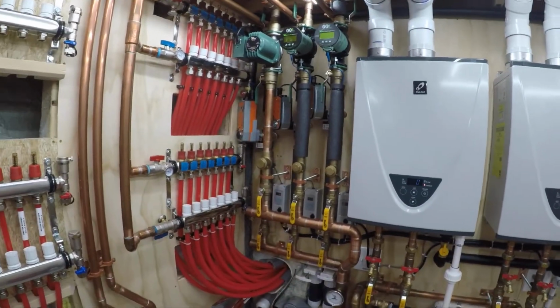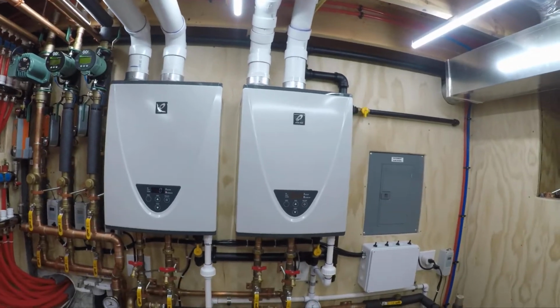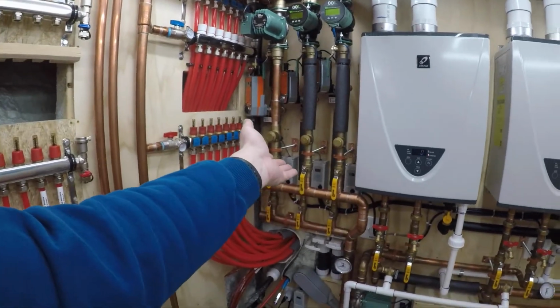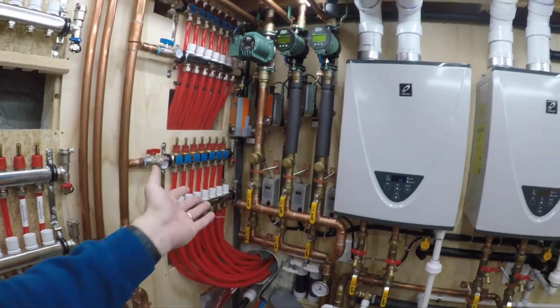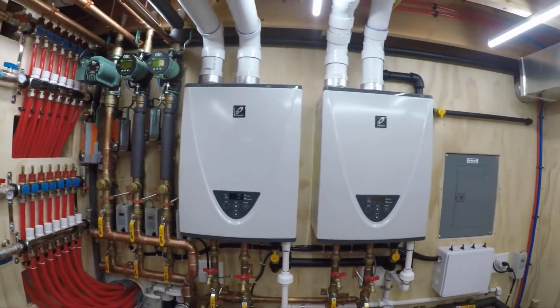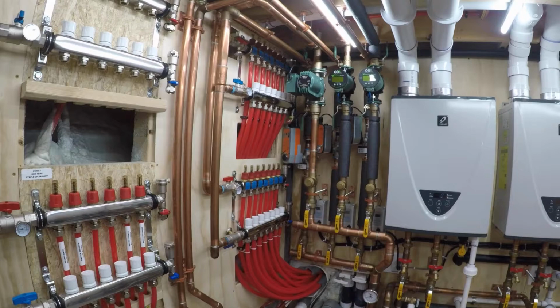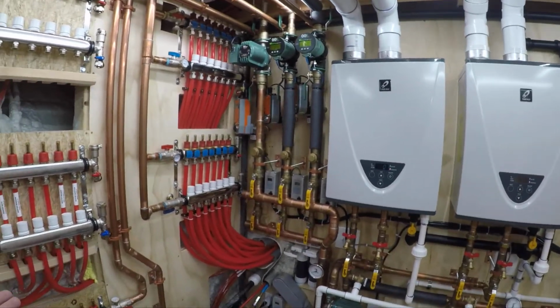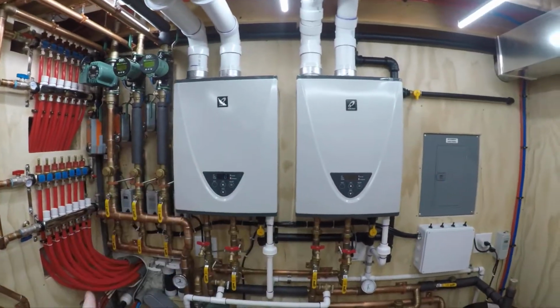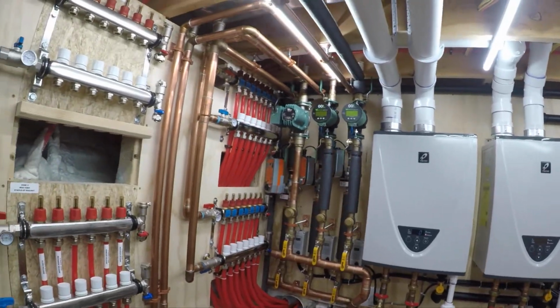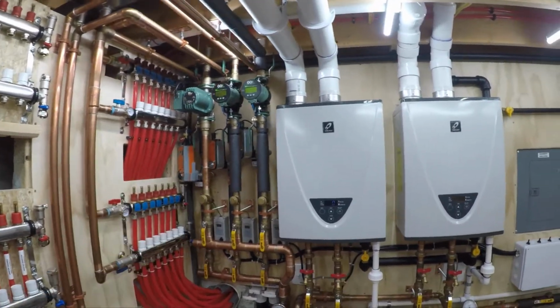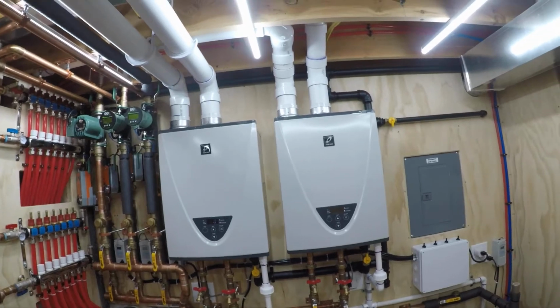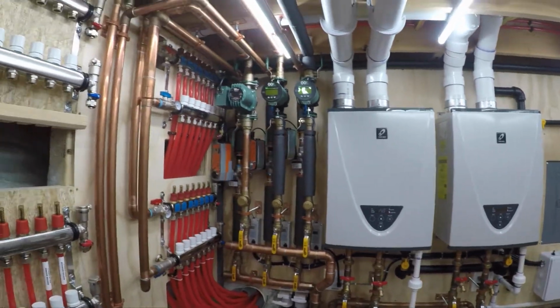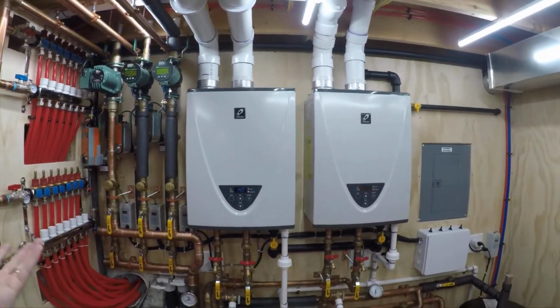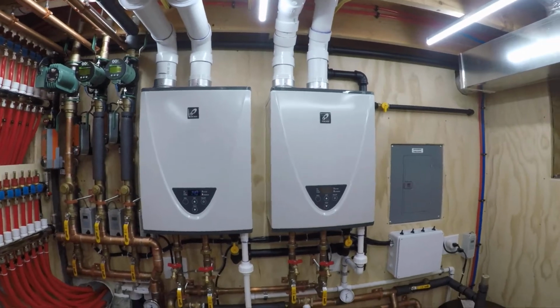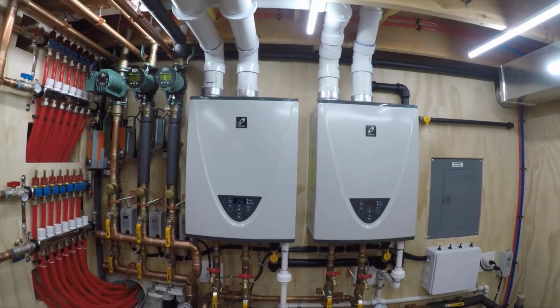Initially, you're going to get a hard hit. You're going to use 300+ thousand BTUs because you've got 20-degree glycol coming back. But it's short-lived. Within 15-20 minutes, you're up to 60 degrees coming back, and the BTUs drop. Within an hour, you're up in the 70s and you're using, I don't want to say nothing, you're using something because you're dumping BTUs out to the driveway, but you're using 175, 180,000 BTUs. It's really not. You could get away with one unit.